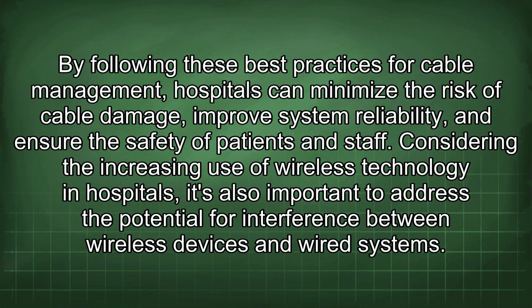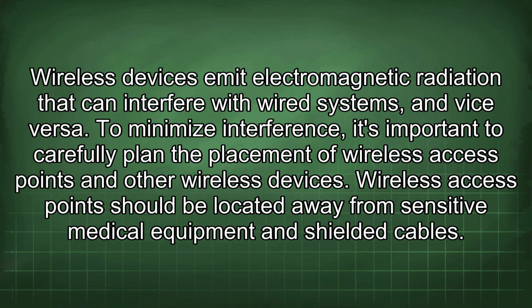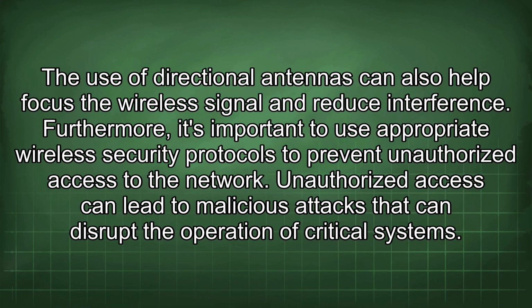Considering the increasing use of wireless technology in hospitals, it's also important to address the potential for interference between wireless devices and wired systems. Wireless devices emit electromagnetic radiation that can interfere with wired systems, and vice versa. To minimize interference, it's important to carefully plan the placement of wireless access points and other wireless devices. Wireless access points should be located away from sensitive medical equipment and shielded cables. The use of directional antennas can also help focus the wireless signal and reduce interference.